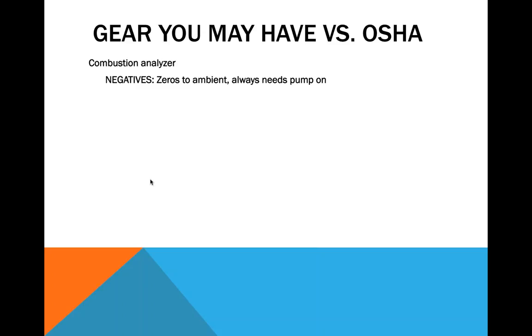So you'd always have to make sure you were referencing it in an area that had no CO and normal oxygen levels. Because of the way the sensors are embedded in the device, a combustion analyzer is purpose-built for monitoring flue gas. So you're always going to need to have the pump running and the probe out, checking the area around you with a combustion analyzer. And again, the zeroing might throw off the ability to detect some of those low levels. On top of that, it does not monitor combustible gases with an LEL output, and it does not monitor hydrogen sulfide.